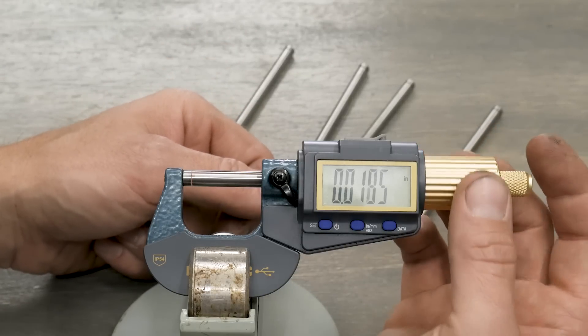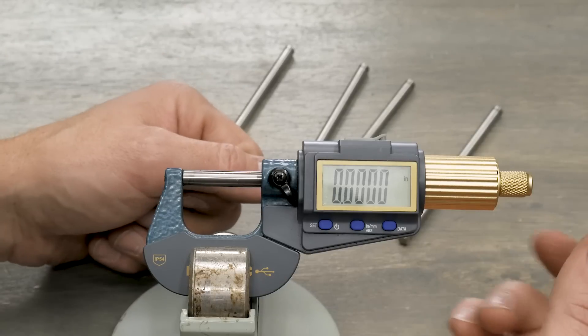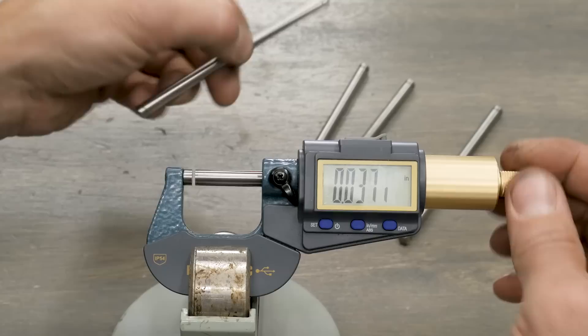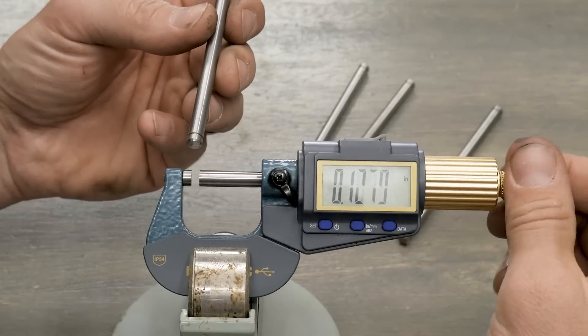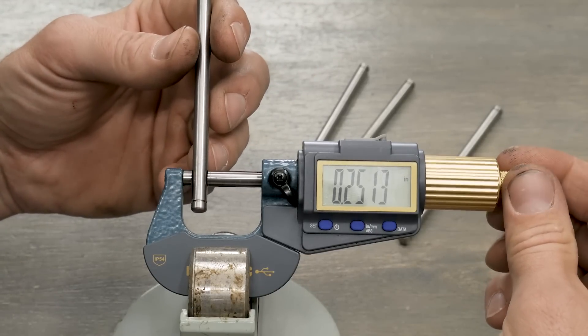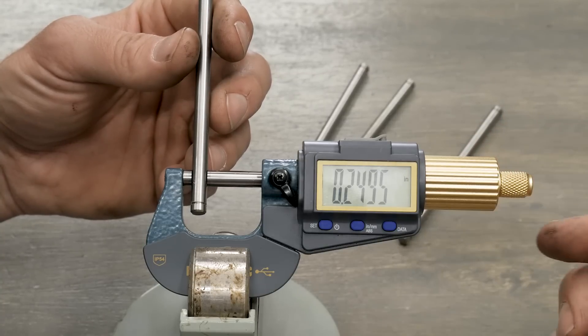Okay, so the first thing we're going to do is check our zero. I'm going to click that against the instrument closed, and that gives us all zeros, so that's good. We can open this up with the knurled knob to more quickly change our adjustment range here. And then I'm going to hold it perfectly perpendicular while closing the dial and let it click.